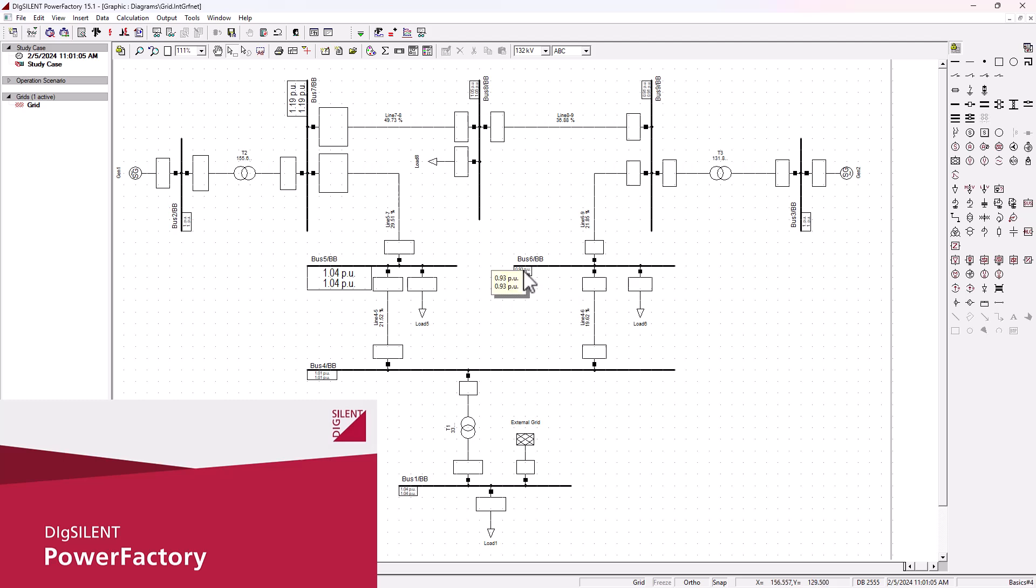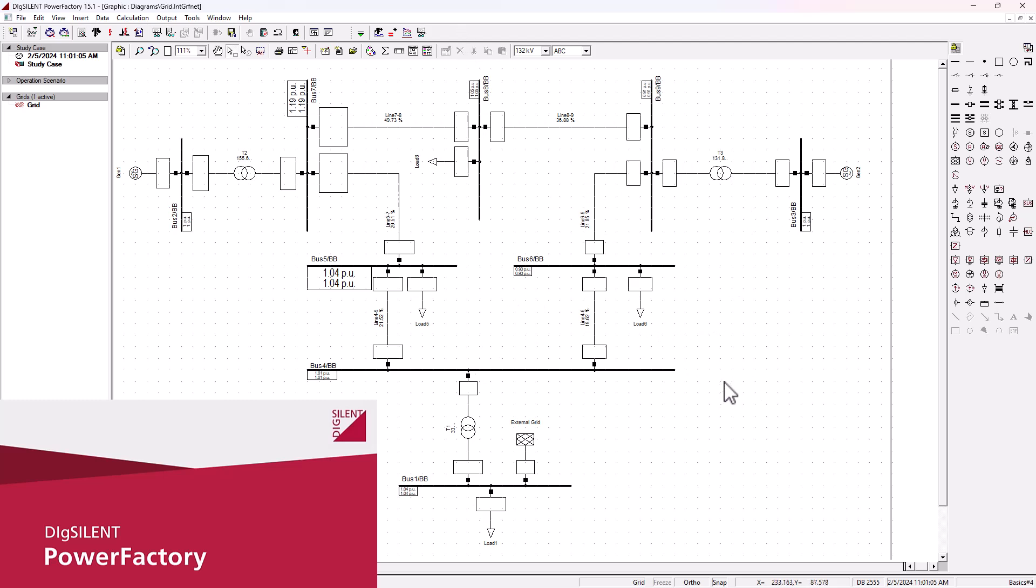After the execution, you're going to mostly monitor the different voltage levels on each one of these busbars. You can see this busbar here, busbar 6, is the most affected because the voltage is dipping to 0.93. You can also observe the line loading as well as the transformer loading in the stability analysis.